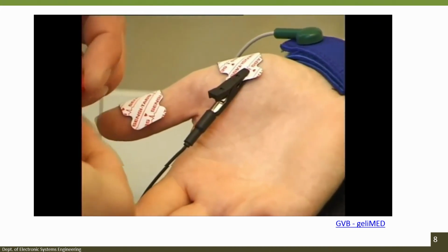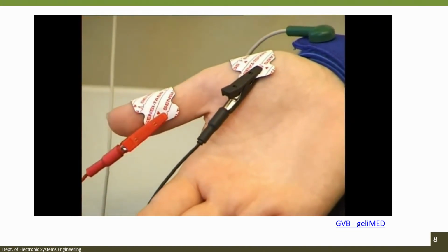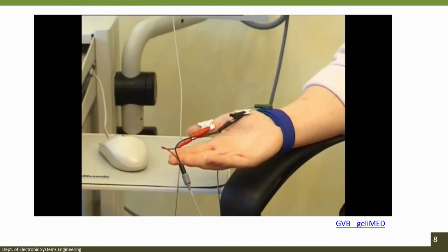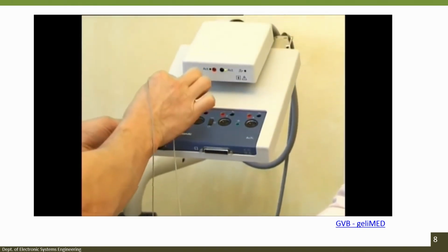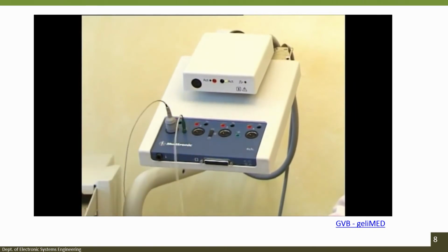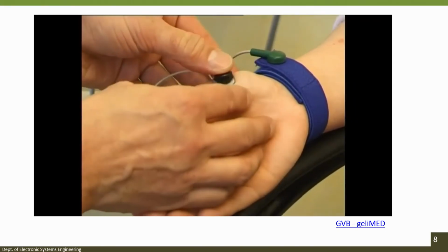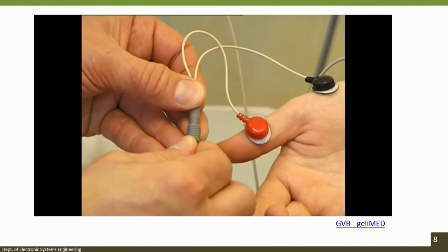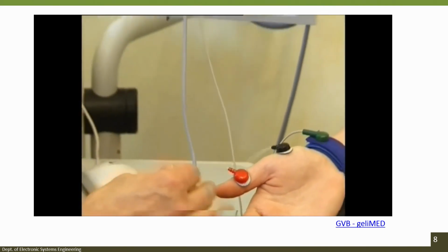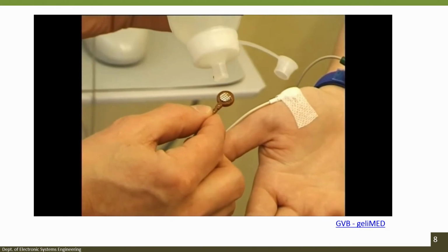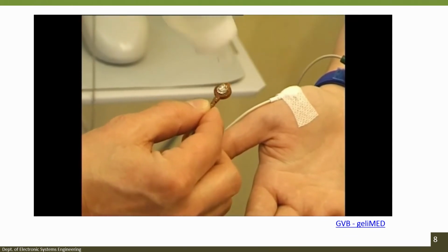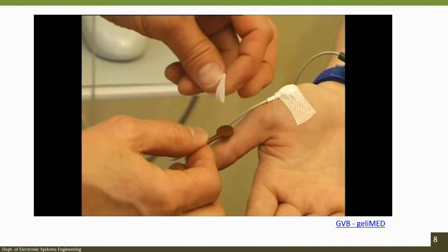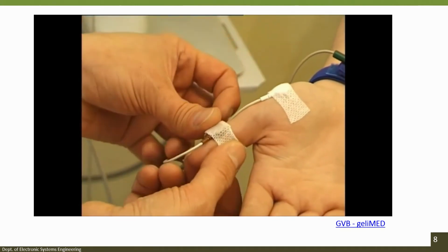In this case, tab adhesive electrodes with crocodile clip lead wires are used and connected to the EMG instrument using a multifunctional cable. Various types of multifunctional system electrodes can be connected to this multifunctional cable. However, snap cables that fit the multifunctional system and snap adhesive electrodes can be used as an alternative to the crocodile clip cables and tab electrodes. Waffle electrodes are a further alternative. However, electrode gel should be applied prior to use to guarantee a good electrode resistance. The electrode itself is attached using adhesive tape.